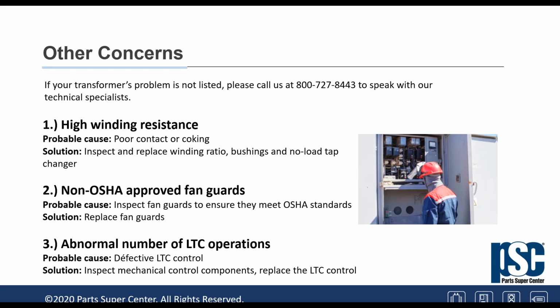Testing, high winding resistance. Well, this is a very important thing. Usually there is a de-energized tap changer on these large power transformers. The de-energized tap changer is nothing more than a means to change the ratio on the primary side, the de-energized side. The problem is that these usually have a stationary contact and a movable contact. They are pressed one against the other. And the pressure displaces the little bit of oil that used to be cooling down the contact. So that's why we recommend, at least once a year when we can shut down, to operate the de-energized tap changer, because that will replace the thin surface of oil that keeps the contact cool.